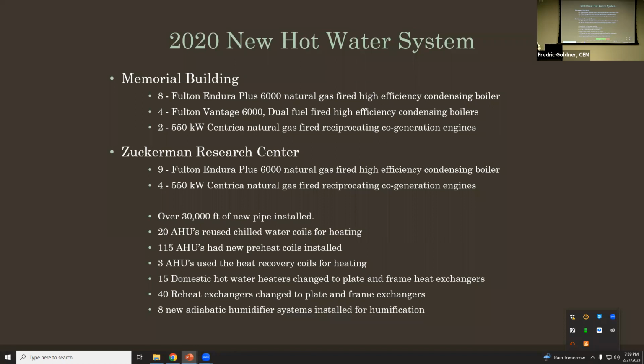Now, what are you going to say about what happens to all the other buildings? We were just going to be able to shut them down, button them up, and pray for the best if it was an extended gas outage. In the Zuckerman building, we had 9 boilers installed, and also we added cogen. The original design was 4 units for the main campus for the Memorial building and 2 for Zuckerman. But when we got into design, structural couldn't handle 4 in Memorial, so we flipped the 2 over to Zuckerman because it was a newer building.